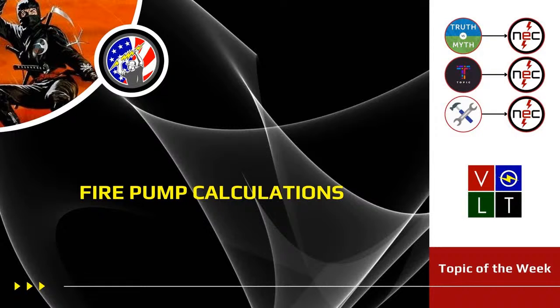Then I'll tie the voltage drop portion into fire pumps, because when you go over there and look at your voltage drop calculations, it's going to tell you that you're going to have 15% for the voltage drop, but that's for the starting. Now when you get into the running portion of it, it says 5%, and that's where you got voltage drop, and then you got voltage drip, is what we like to call it.